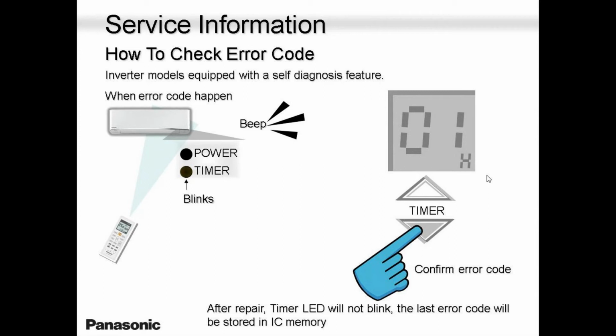So when the error code happens, the orange light, guys, please remember, there is a difference between the green, which is the power light, and the timer. The orange or yellow timer light will blink. I get calls once a week. Oh, Paul, I have an error code. What's the error? What's it doing? Oh, the power light was blinking. The power light, when it blinks, it means the unit is in defrost. But when there is a problem with the unit, it's the timer light that blinks.